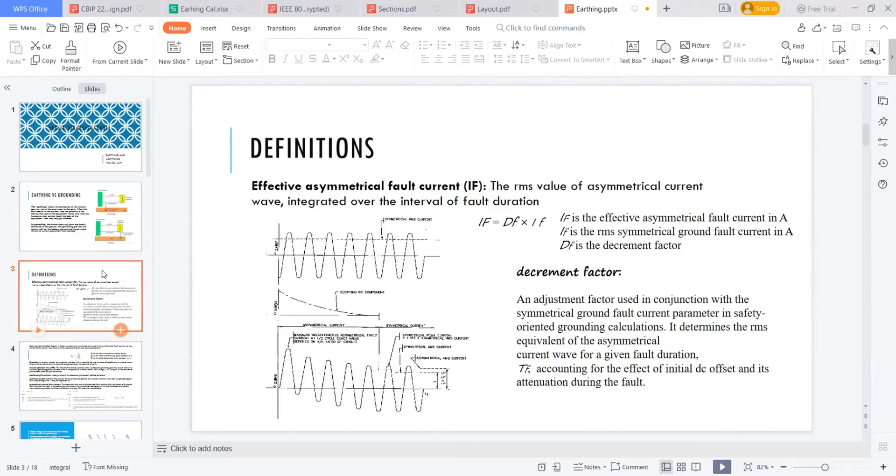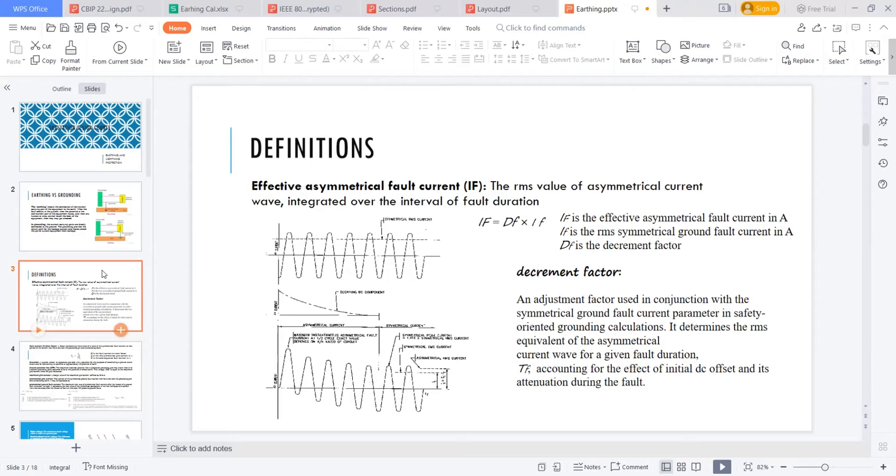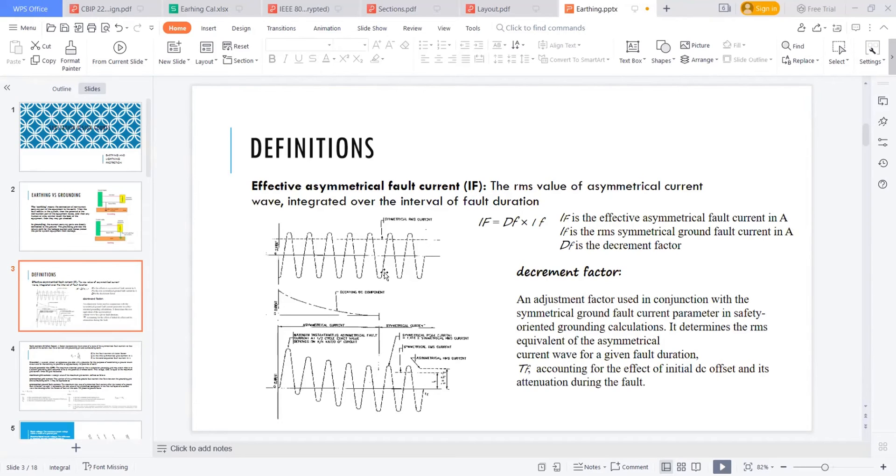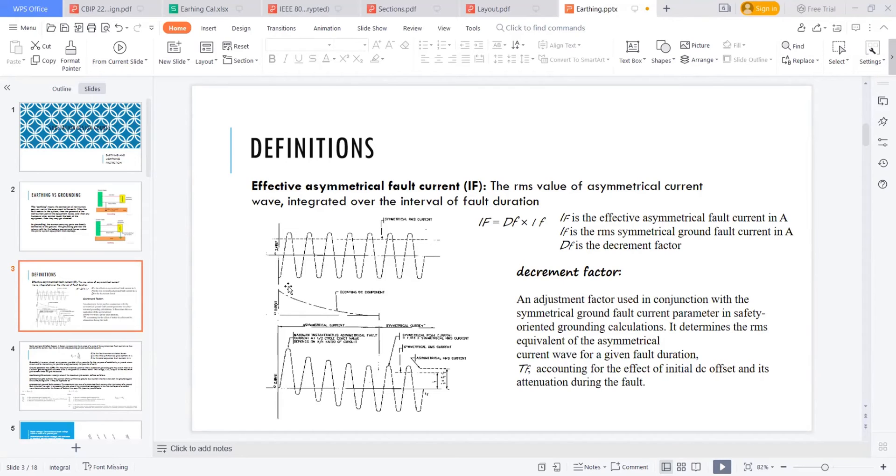The first one is the effective asymmetrical fault current. I am talking about the term effective asymmetrical fault current. What is this? The RMS value of asymmetrical current wave integrated over the interval of fault duration. This part we discussed in our breaker session that this is a symmetrical RMS current, but when a fault occurred due to the presence of DC component in the first cycles, this DC component may lead this waveform towards the up. The magnitude is very high.